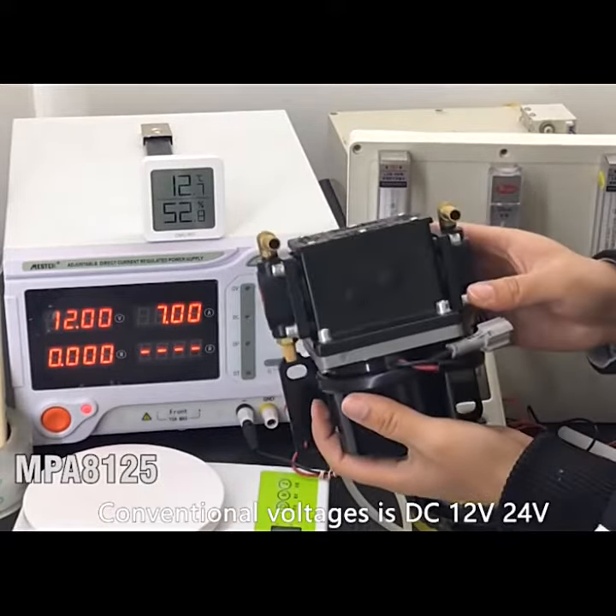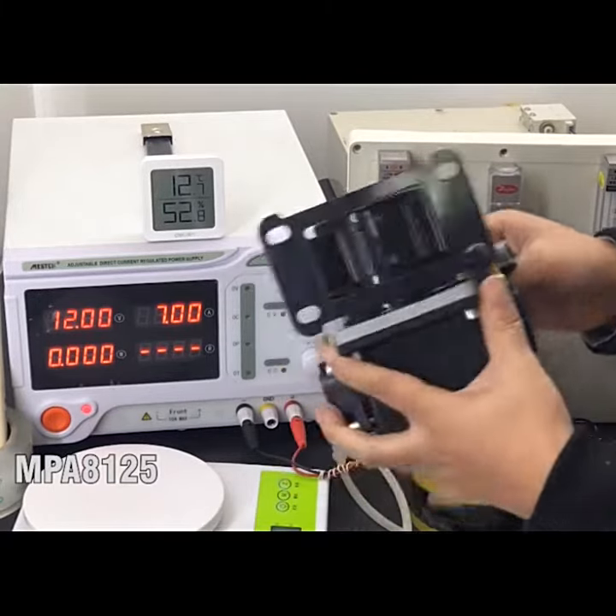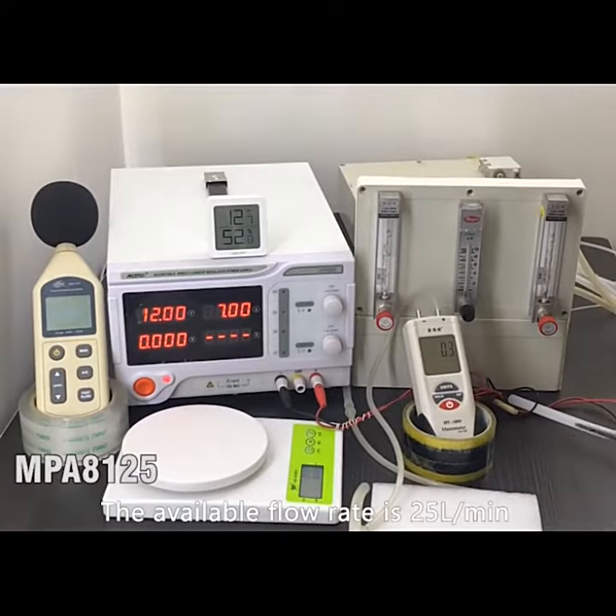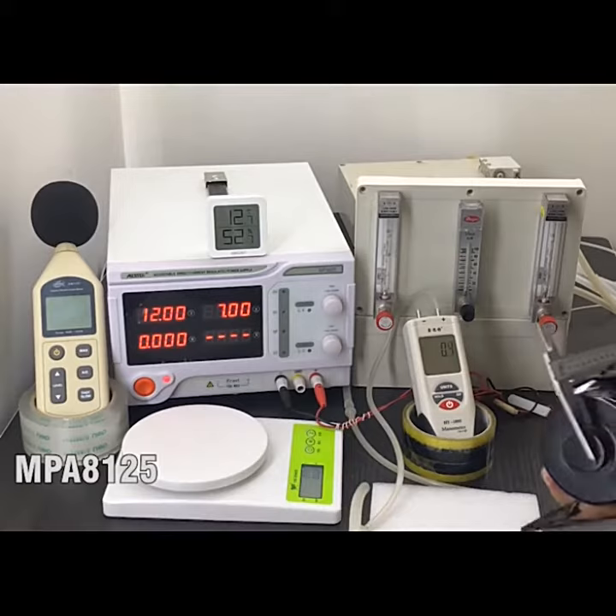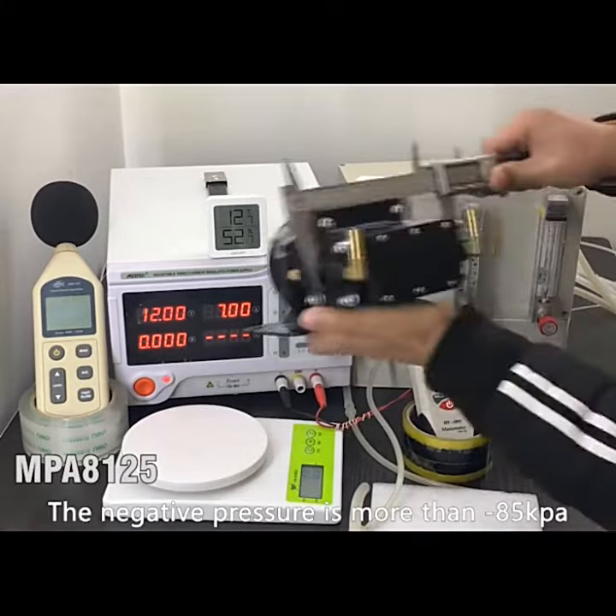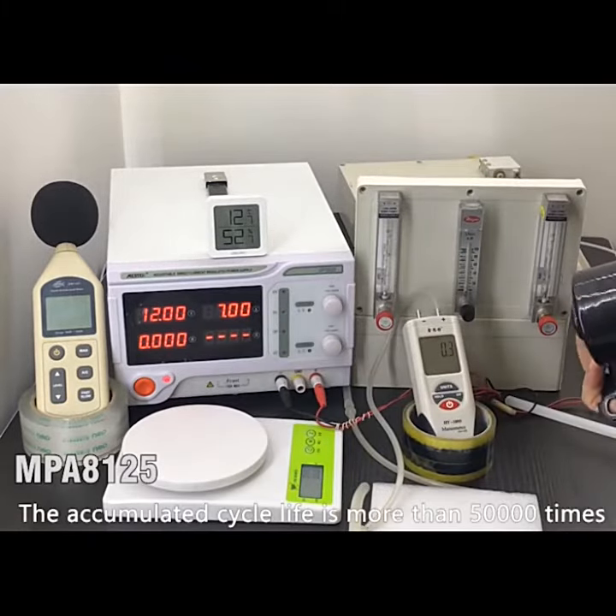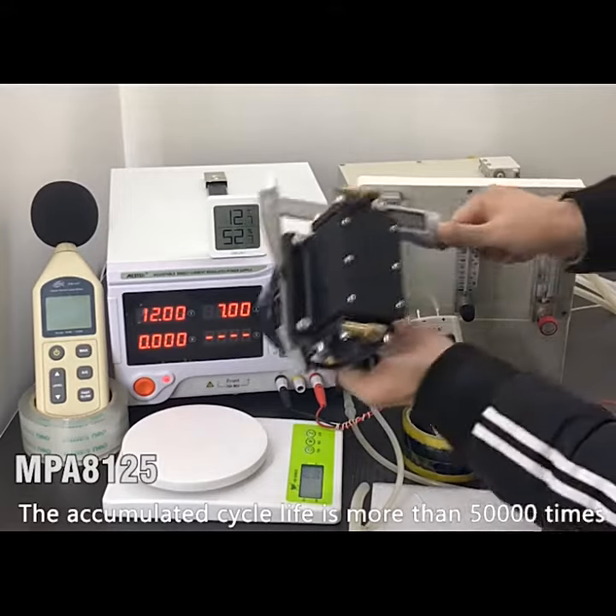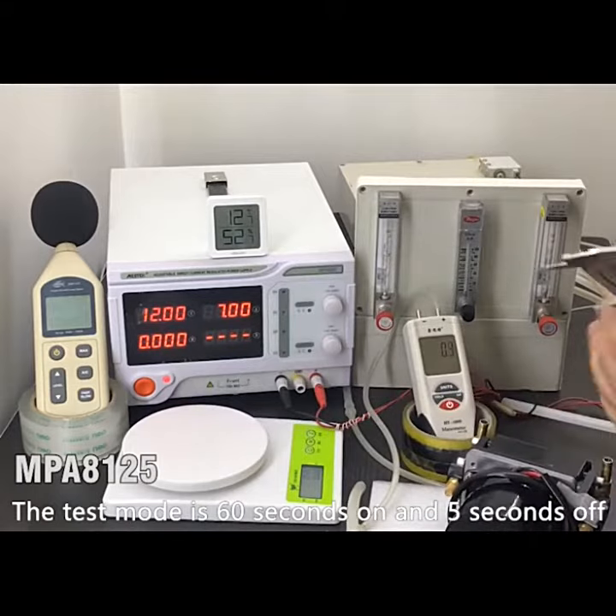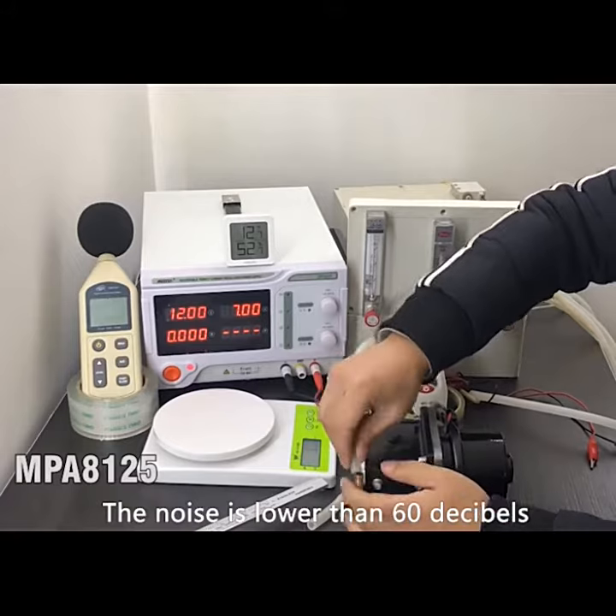The conventional voltage is DC 12V or 24V. The air flow rate is 25 liters per minute. The negative pressure is more than 85 kPa. The accumulated cycle life is more than 50,000 times. The test mode is 60 seconds on and 5 seconds off. The noise is lower than 60 dB.